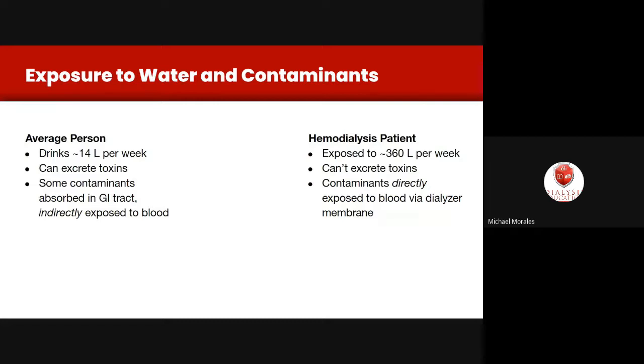Hemodialysis patients' exposure to water through dialysate is up to 360 liters per week. The math: running dialysate for four hours at 500 mL/min equals 240 minutes × 500 = 120,000 mL, or 120 liters per treatment. Times three treatments per week, that is 360 liters per week — and that is at a 500 mL/min dialysate flow rate; the flow rate could be higher.